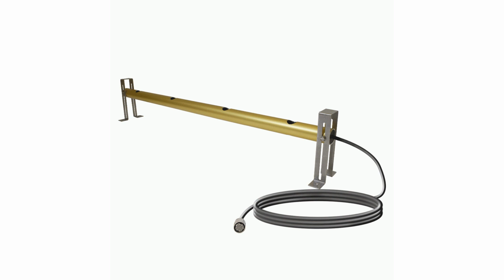Say your duct is 2 by 2 feet, you probably will have two probes fitted on the horizontal lines and two probes fitted on the vertical lines. So that's how the number of sensors, or the number of probes which you take, is usually calculated. There is a chart where you can see, based on the length of your duct, how many probes you need.